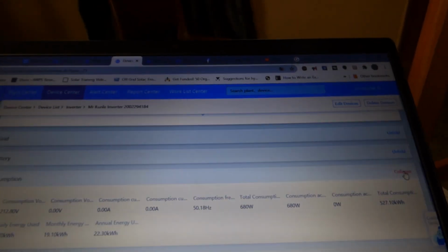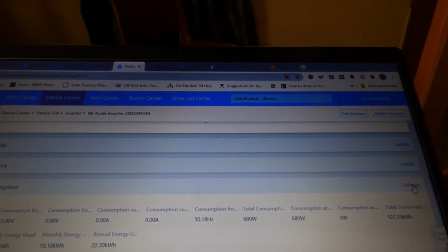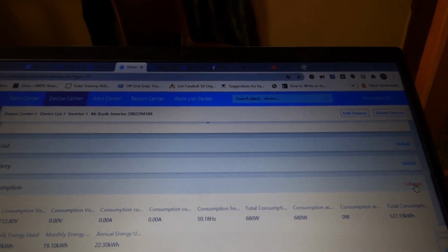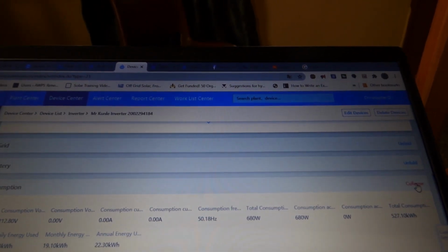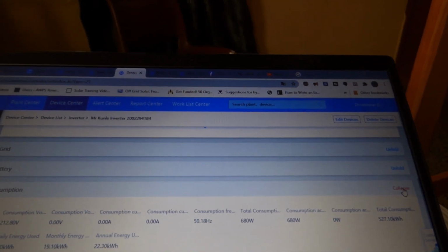What it does is, whatever is coming from PV is charging the batteries, and then whatever load they have is coming from the grid. Now, once the generation exceeds the combination of both, it will ignore the grid, it will power the loads, and then put the excess to the battery. So that's how time of use works here.